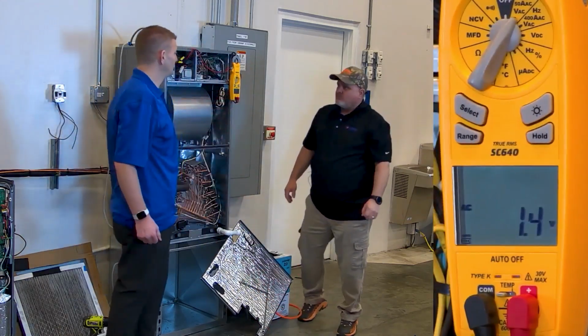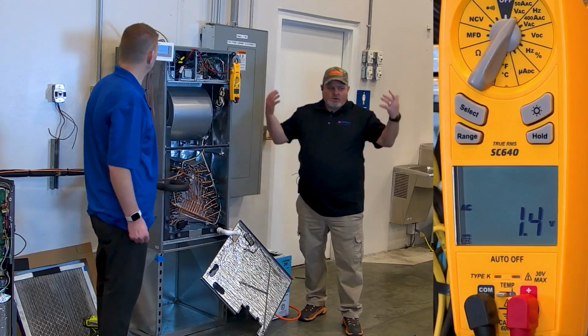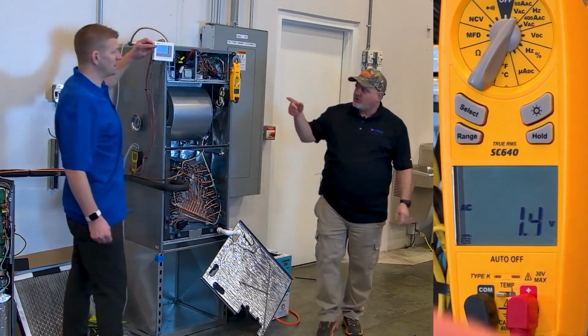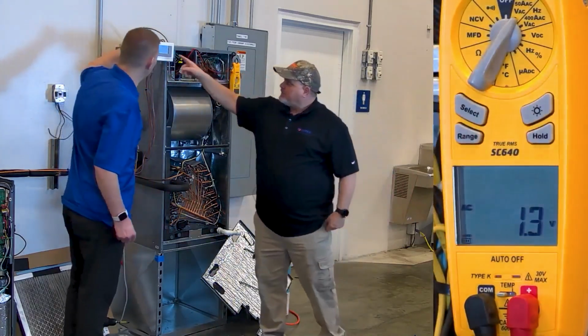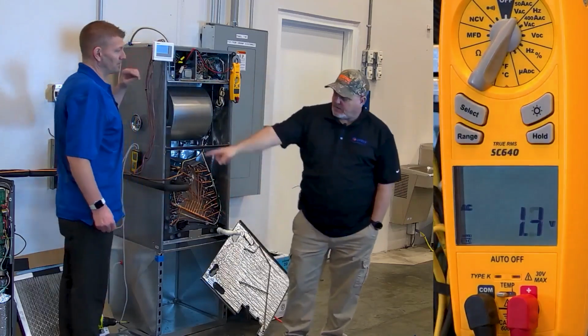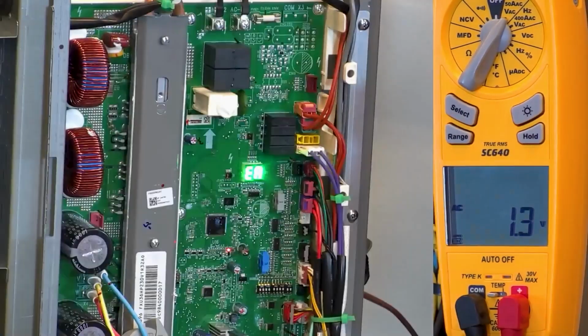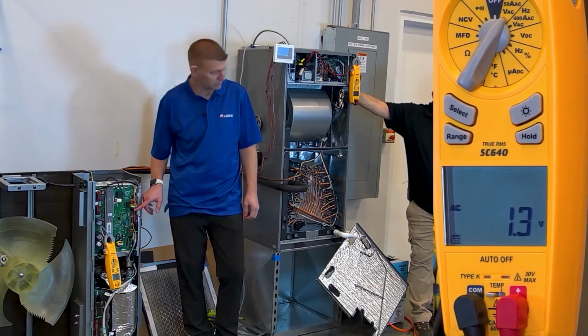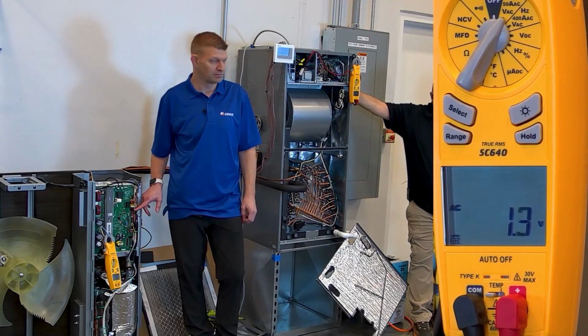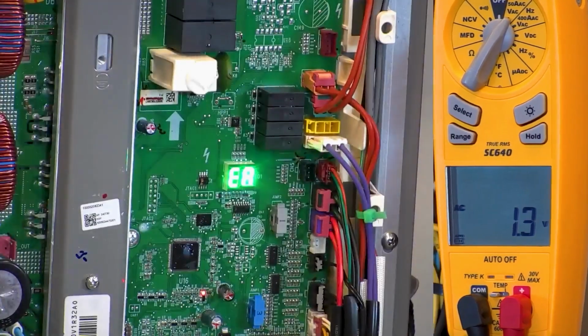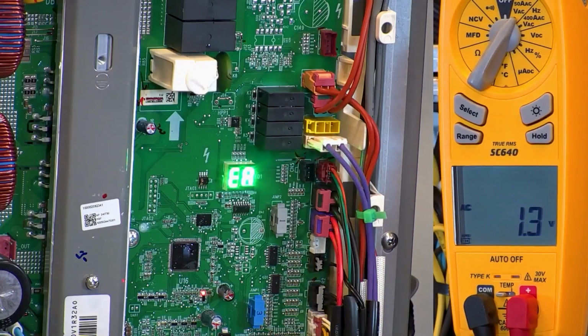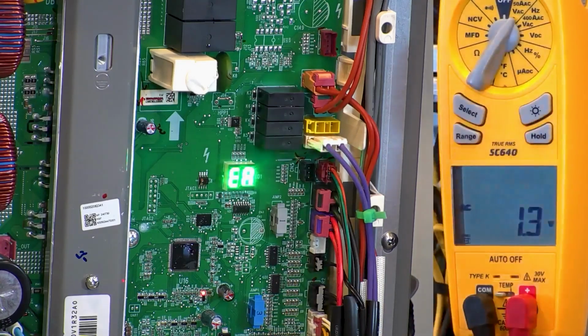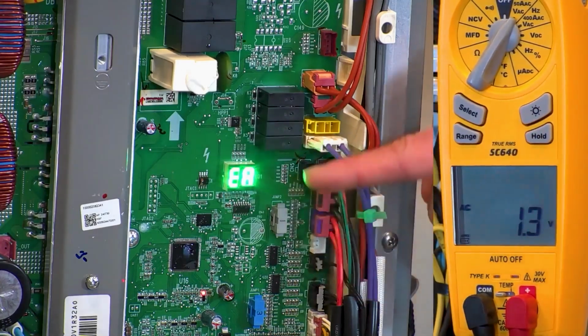Instantly killed power. That's what they told us. And as you can see, this displays refrigerant detection error. Yep, and the outdoor unit has an EA code. Now that audible alarm is extremely obnoxious, and it will go away once the sensor is cleared.